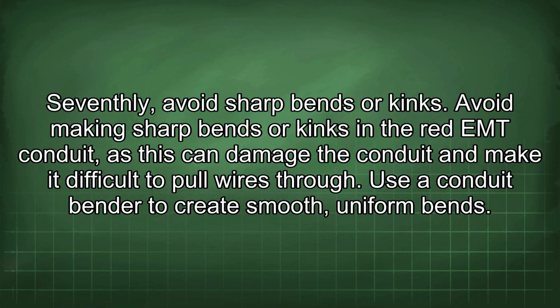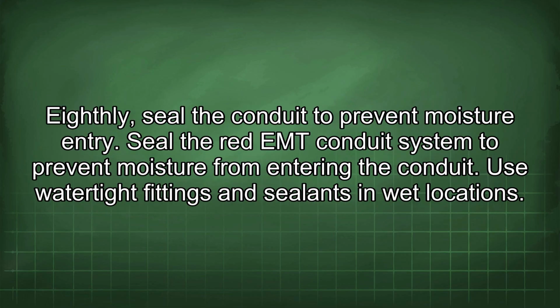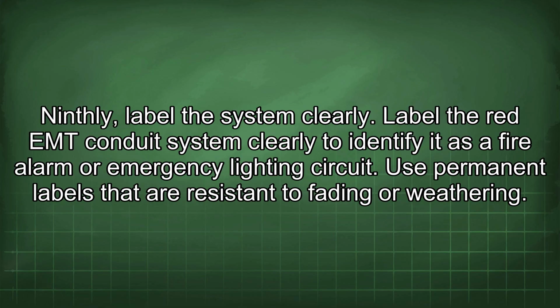Seventhly, avoid sharp bends or kinks. Avoid making sharp bends or kinks in the red EMT conduit, as this can damage the conduit and make it difficult to pull wires through. Use a conduit bender to create smooth, uniform bends. Eighthly, seal the conduit to prevent moisture entry. Seal the red EMT conduit system to prevent moisture from entering the conduit. Use watertight fittings and sealants in wet locations. Ninthly, label the system clearly.